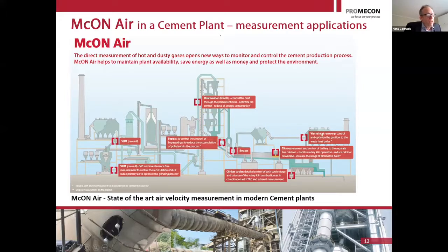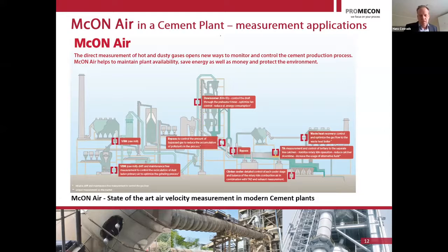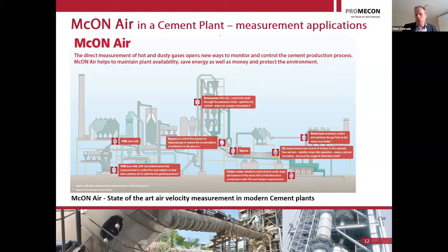Another major application is the tertiary air duct measurement. It has become very popular but is very difficult to measure — even we struggled initially to make it work reliably. We now have good references and have found a way to serve all tertiary air duct configurations. This is very important for NOx formation in your pre-calciner: how much combustion air are you putting in? Most of the oxygen comes from the tertiary air, so proper measurement is needed for control.